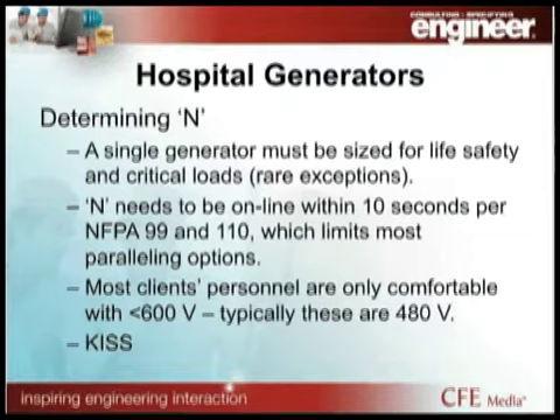We want those two branches to be online within 10 seconds, and most of our clients want it that way too. It's worth talking about that most hospital clients, facility directors, the people that are on the ground, want things simple. And even medium voltage, which engineers like us tend to think of as straightforward and simple, makes them a little nervous. They always think about that engineer or facilities engineer that's on site in the middle of the night when there's a loss of power and something goes wrong. So I can't stress enough: keep it simple, keep it real simple, and that's what has kept clients coming back to me, and that's what most of my clients share with me over and over again.